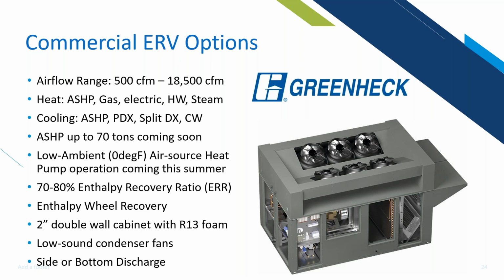That's great because you can hit an airflow range between 500 CFM and 18,500 CFM, and you can usually achieve an enthalpy recovery ratio from an ERV unit between 70 and 80% with an enthalpy recovery wheel. So this is a unit we've been selling for a long time in this market, and we're excited to say that it's going to be updated for our market, and we'll be able to really go for any projects that we'll typically be releasing after August 5th, just so you know.